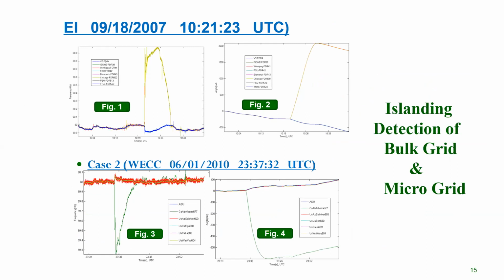So here's some older information on islanding phenomena we detected. This is a large system island, where a large piece of the grid becomes independent. This could be okay, or it could be very dangerous, because you don't necessarily balance the load in the system, and you may end up losing load or having to shut down generation. That's not desirable, and people try every effort to avoid it. But this can actually be detected without too much difficulty. This also ties to microgrid—basically a microgrid is a system prepared to be islanded, while most systems are not prepared to be islanded.